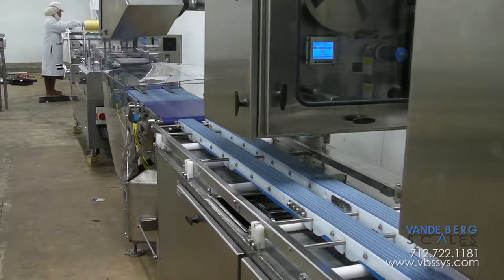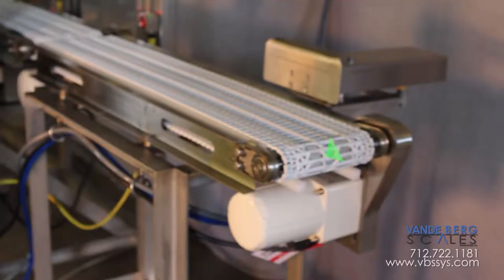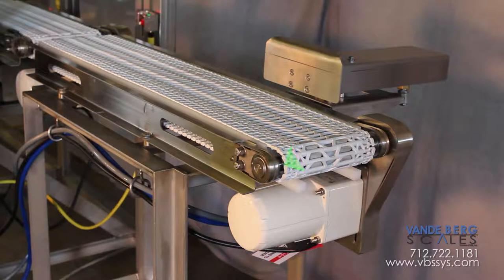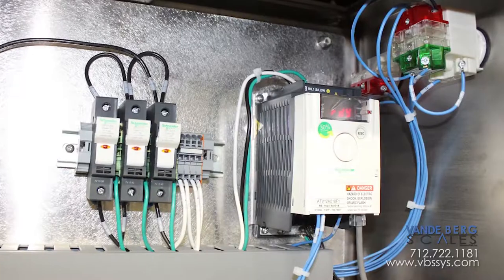Our conveyor design is simple, yet extremely robust, using a single-shaft design with UHMW belt runners allowing easier clean-through. The stainless solid-square drive shaft uses heavy-duty stainless bearings to assure long, trouble-free life. No toy bearings here. Conveyor drives are designed with easy-to-obtain, epoxy-painted, NEMA 4X, wash-down rated, variable AC motors driven by easy-to-obtain variable frequency drives.